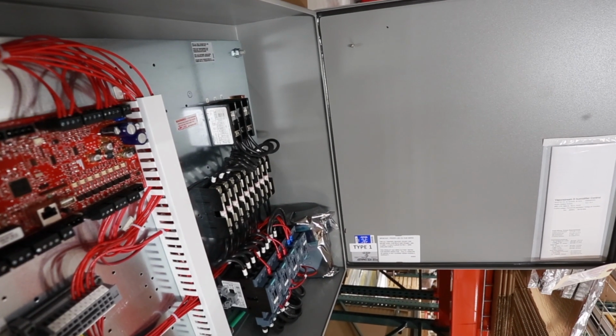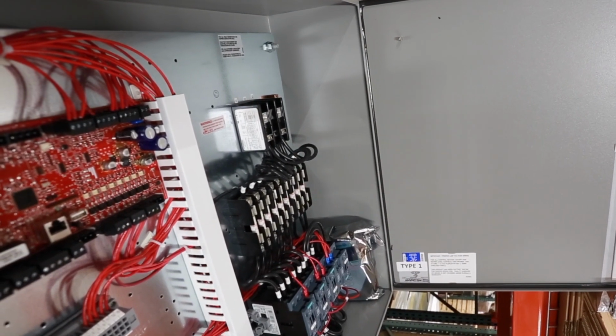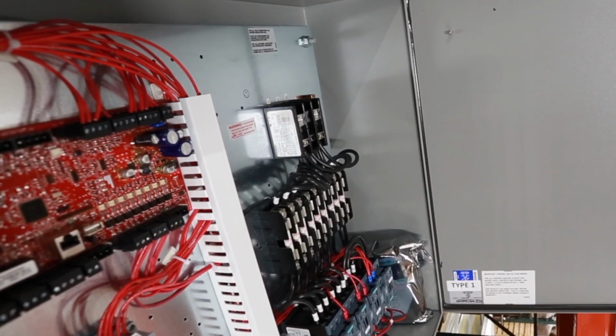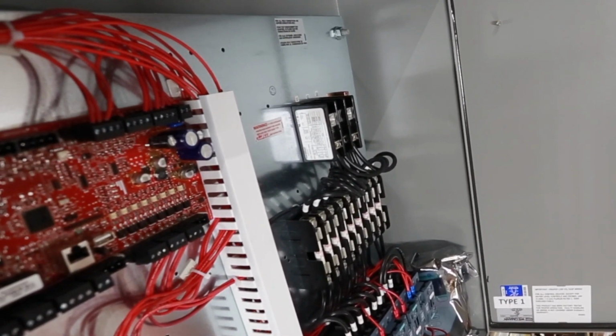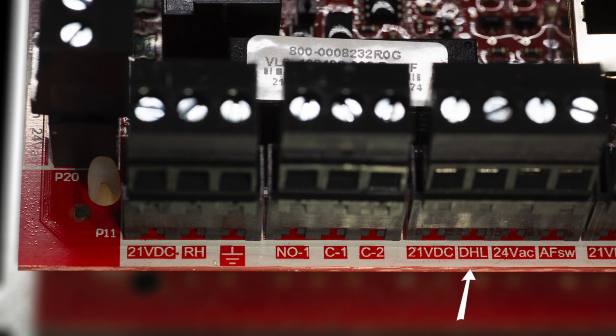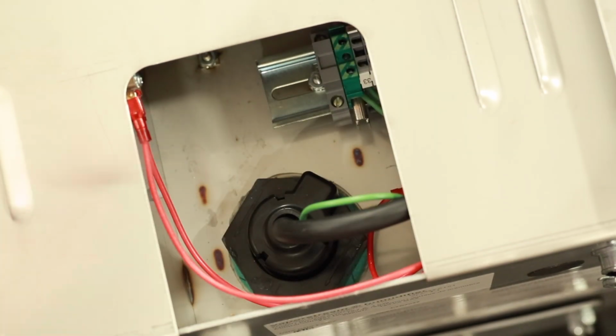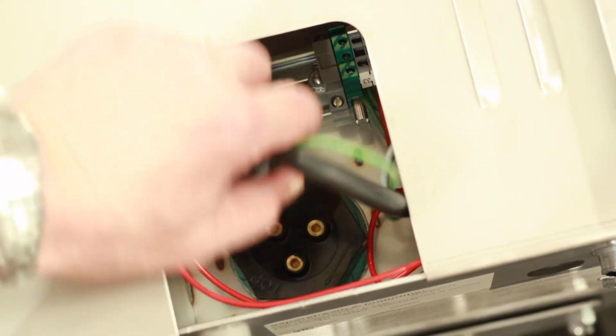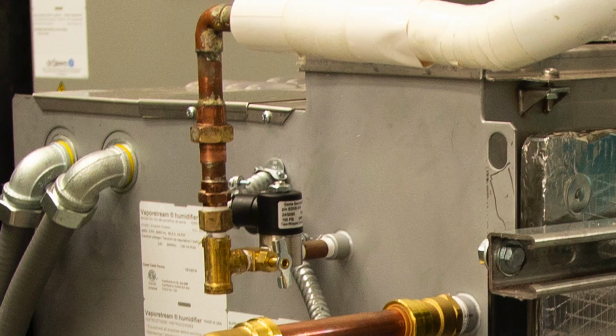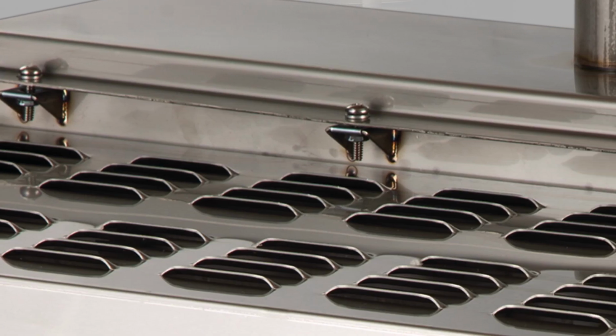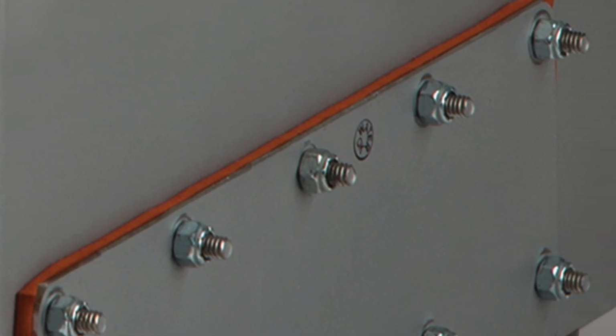At least annually and whenever maintenance is performed, all safety devices in the control circuit should be cycled on and off to verify they are functioning. These include a high limit switch, airflow proving switch, and low water level probe. Pull out the probe plug. Fill valve should energize. Inspect the tank and gasket for leaks.